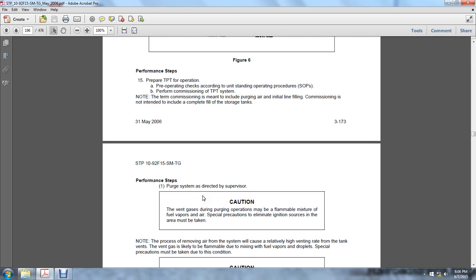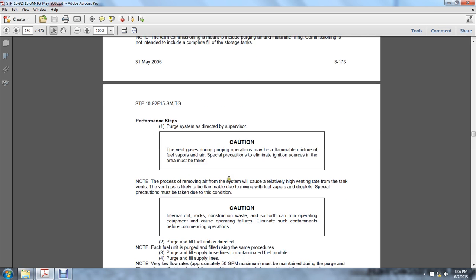1. Purge system as directed by the supervisor. Caution: the vent gases during the purging operations may be flammable. Make sure the fuel vapors are accounted for, and special precautions to eliminate ignition sources from the areas must be taken. The process of removing the air from the system will cause a relatively high ventilation rate at the tank vents. The vent is actually flammable due to the mix of fuel vapors and droplets, and special precautions must be taken due to this condition. Caution: dirt, rock, construction waste, and so forth can ruin equipment and cause operation failures. Eliminate such contaminants before commencing operation.